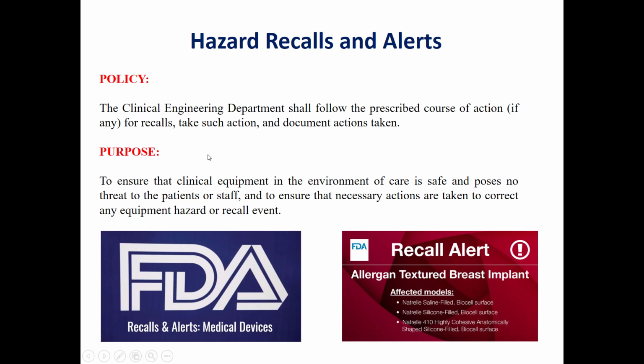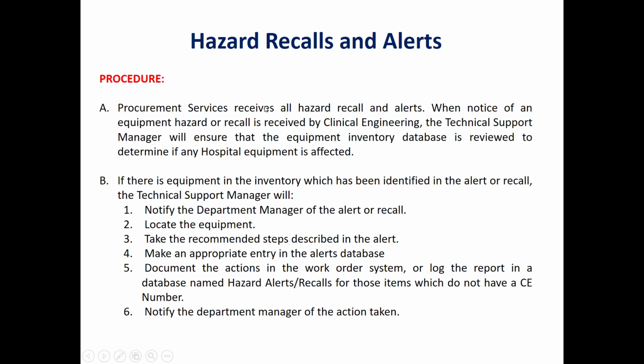So why do we need such a policy? To ensure that the clinical equipment in the environment of care is safe and consequently poses no threat to the patients or staff, and to ensure that necessary actions are taken to correct any equipment hazard or recall event. In order to execute such a policy, we need a procedure.